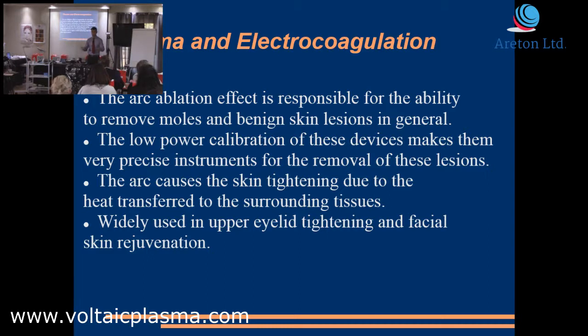As a fundamental exercise, you must do this with any device, because it's meant to teach you two things. One, understand firsthand how powerful these things are, since it actually burns flesh. Two, if you're using these devices, especially ours, you've got to be able to generate the arc when the device is set at minimum power level.